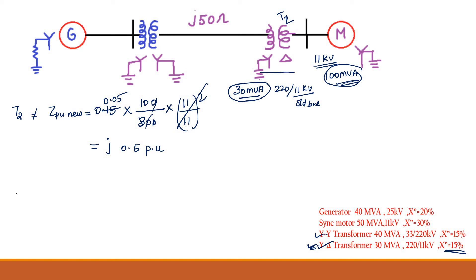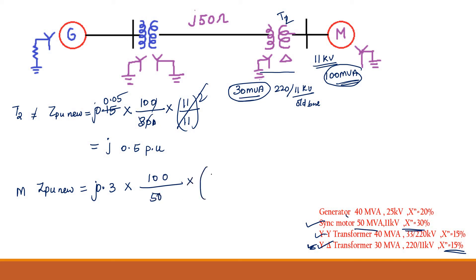Next, I am going to find out ZPU_new for the motor. For the synchronous motor, ZPU_old is J0.3. New MVA is 100, old MVA is 50. Old KV is 11 and new KV is also 11. So the answer is J0.6 per unit. Now we have the per unit value of all the components in the power system.